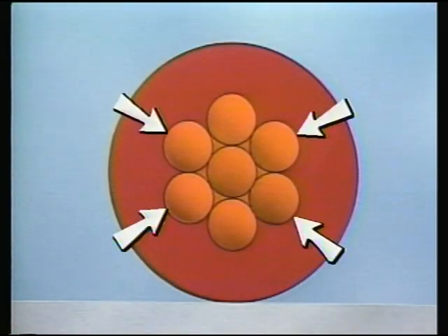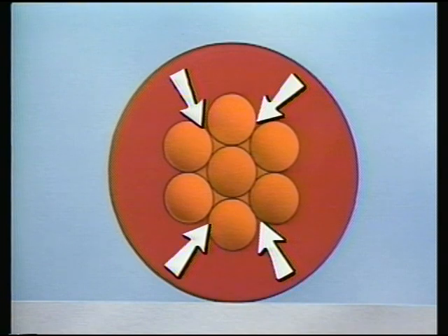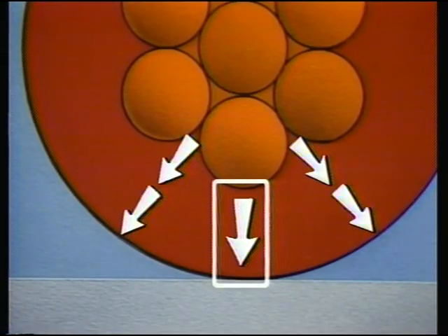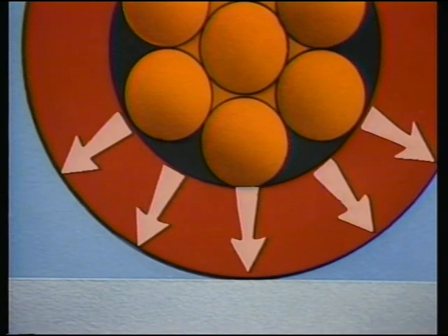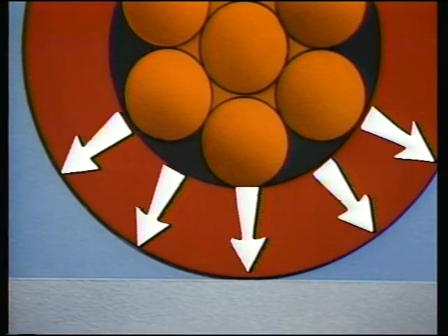Because the conductor is stranded, there are high and low points from which the stress lines radiate. The lines travel a further distance to ground at the conductor low points because the path to ground is longer. Normally, voltage stress would concentrate in areas like this high point, where the insulation is not as thick. But by using a semiconductive shield layer, the cable insulation is given a more uniform thickness around the conductor, similar to what would be provided with a solid or round conductor. This helps reduce any areas of possible stress concentration.